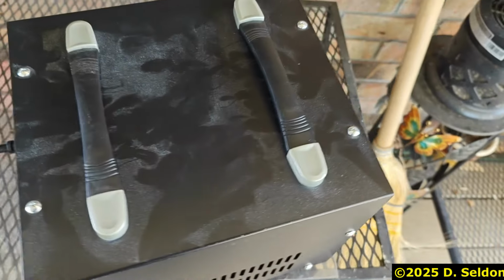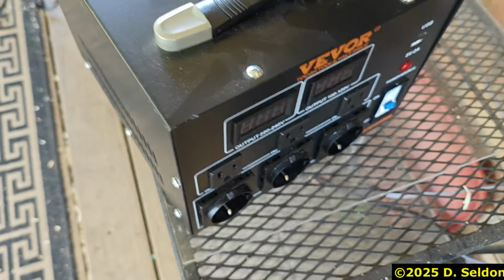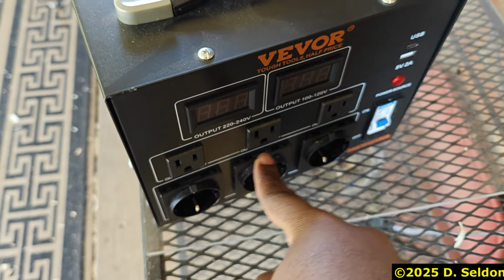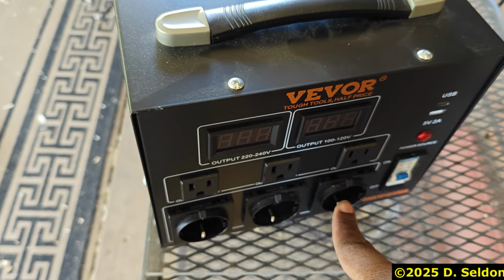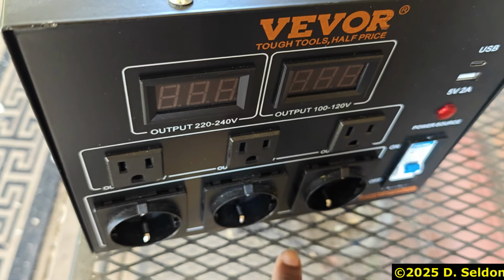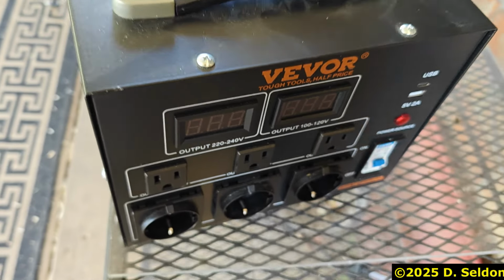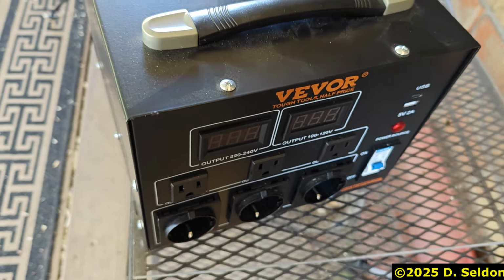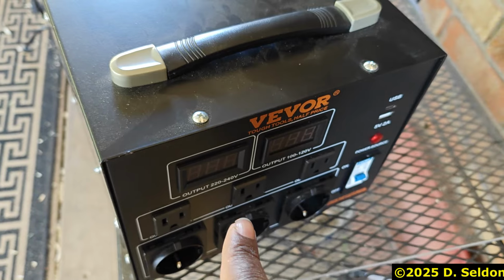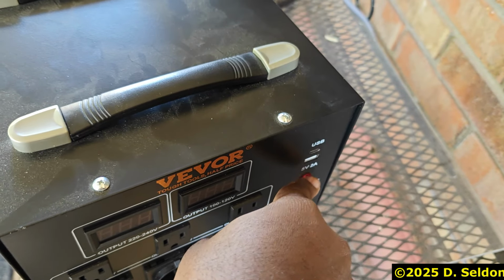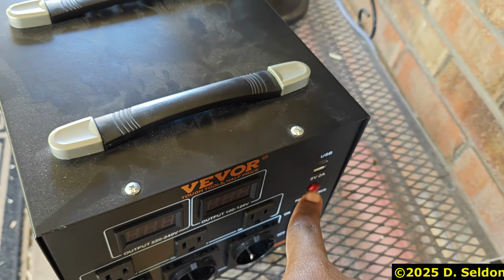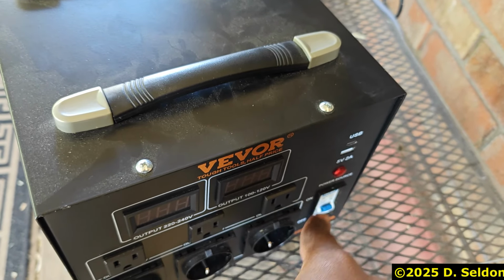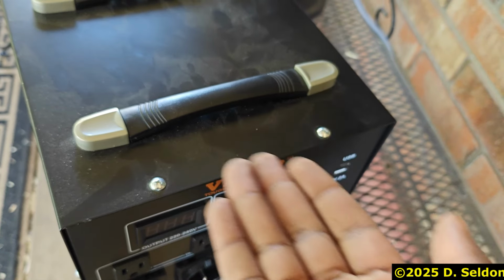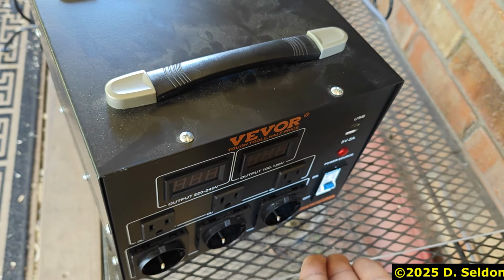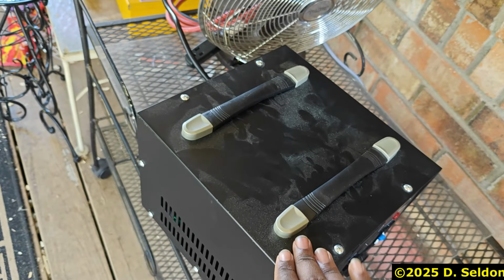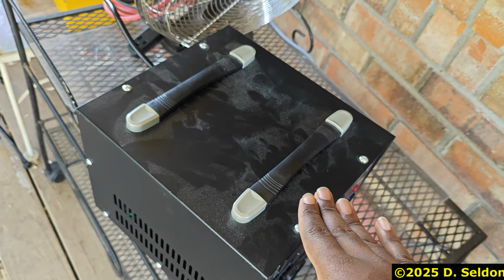When this thing was running the siren, I was getting 240 out of the 120 sockets, and the euro sockets were running at 480. So it let the smoke out, but that smoke wasn't the transformer destroying itself - it was the circuitry that runs all this little nonsense. It's got a circuit breaker here, but it didn't pop because it wasn't drawing enough amperage to trip it effectively. This thing is rated for 5,000 watts, so it should have had enough power to handle that siren.